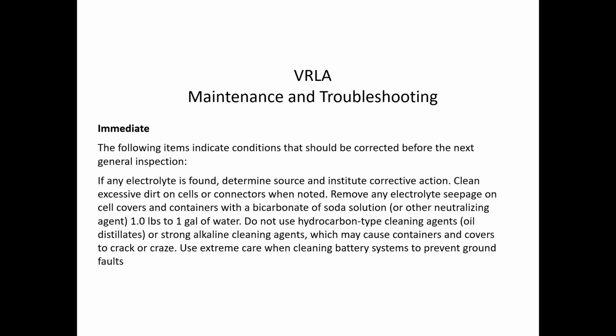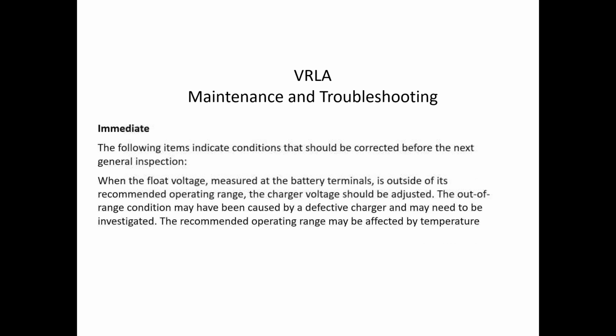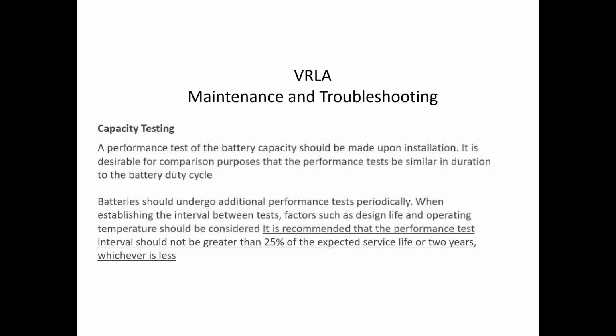So again, any electrolyte found, any kind of leaking cell is certainly cause for concern, further investigation, cleaning. Float voltage: you come in there and find this thing's in equalization, or undercharge. Or this is open circuit or well below voltage. That's something else that's going to require immediate investigation.